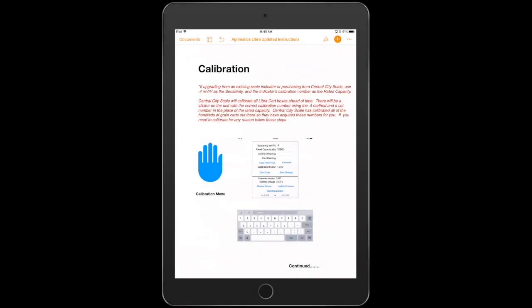In the previous video, we talked about configuration. Now we're going to continue from that and talk about calibration. So at Central City Scale, we use a method called the 0.4 millivolt per volt for the sensitivity method. And this enables us just to use current calibration numbers with all different scale systems. So it makes the calibration very simple.